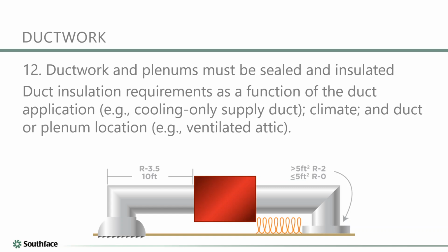In a commercial building, sometimes we see that. There are still small commercial buildings built with insulated ceilings and vented attics just like houses. But a lot of commercial buildings do have their duct systems and their air handlers inside the building envelope. And because of that, they benefit. The duct leakage is not as much of an energy penalty. But as you said, we also have concerns around condensation. We also have concerns around just performance and comfort. I always remind people that whether your ducts are inside or outside of your building's thermal envelope, if 30% of your airflow is going somewhere other than where it's intended to go, you're not going to efficiently achieve comfort.